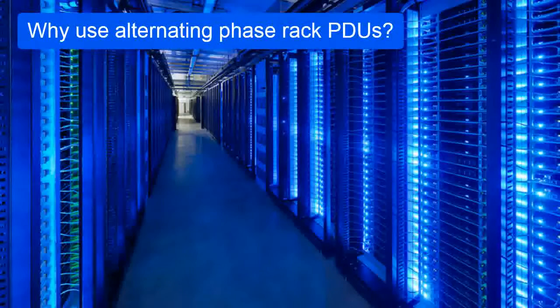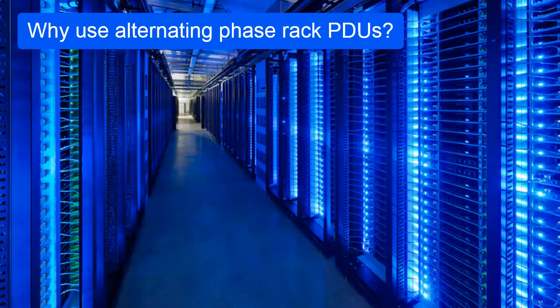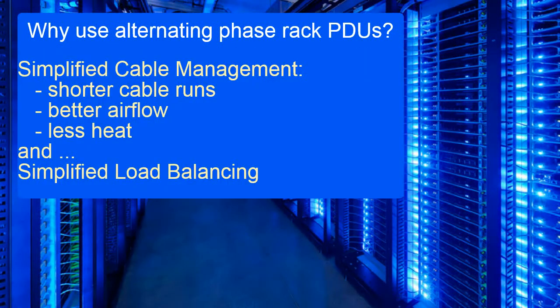So why would you want to use an alternating-phase rack PDU instead of a conventional PDU? The key benefits are simplified cable management and load balancing. You'll end up having shorter cable runs, which result in better airflow, less heat, and a net-improvement PUE.